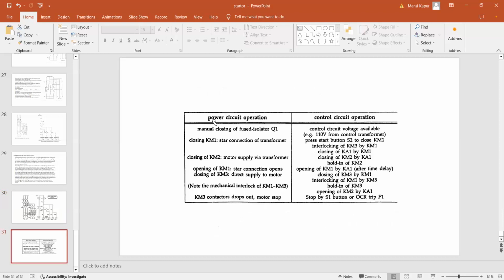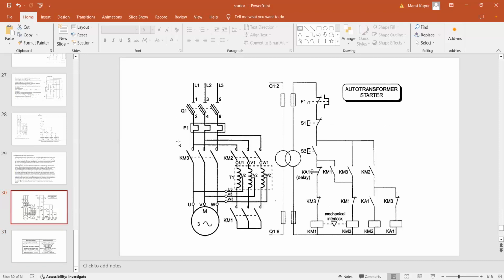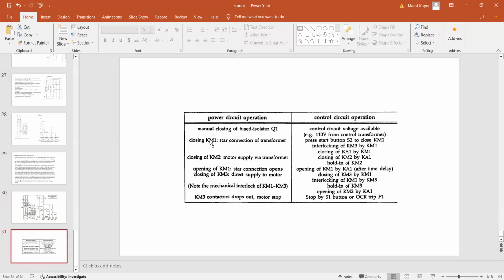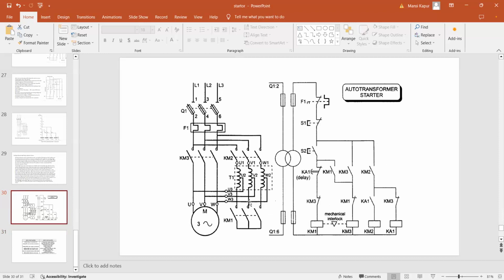So the power circuit operation: manual closing of isolator fuse Q1, this is a manual closer. Closing KM1 gives the star connection of the transformer, this is the star connection of the transformer.